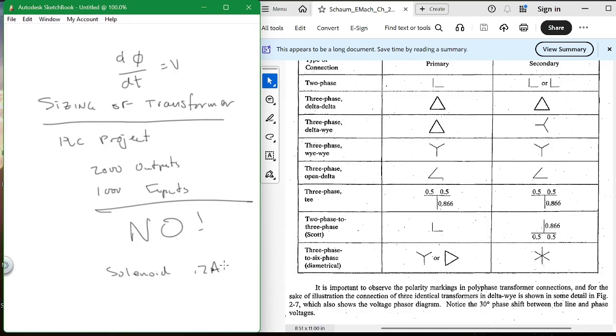Now here's a question: are you going to turn these all on at the same time, and are they all going to have an inrush? Then you have to go with the inrush current. But most of the time you don't have to turn them all on at the same time, so you just go with the standard running current, unless they all have to be turned on at the same time - valid question, you have to ask that. If they don't all have to be turned on at the same time, you go with the running current of the devices, multiply that times the voltage at which they're output, 110 volts or whatever, and that comes up with a wattage.